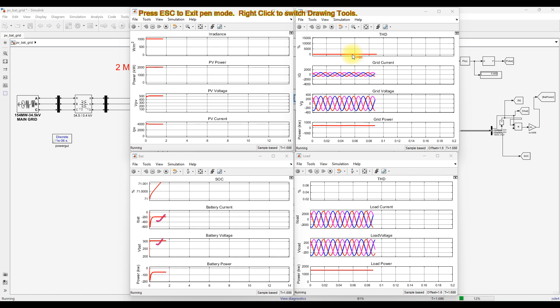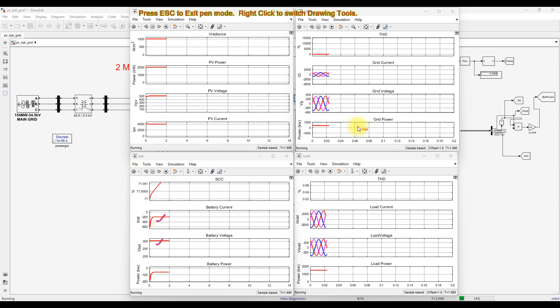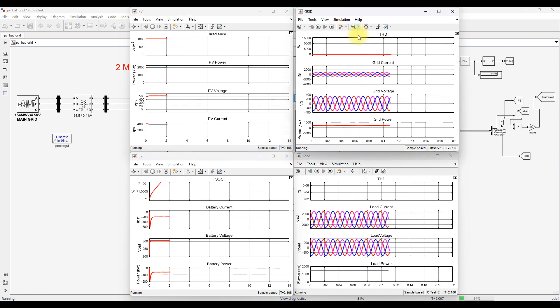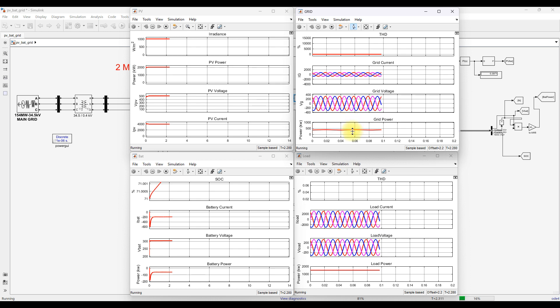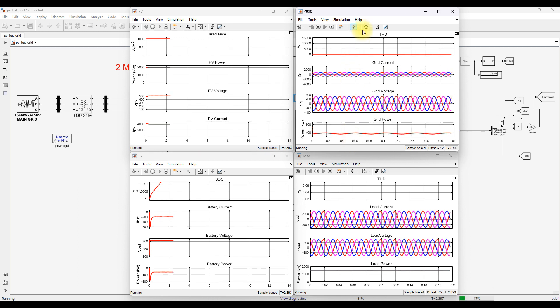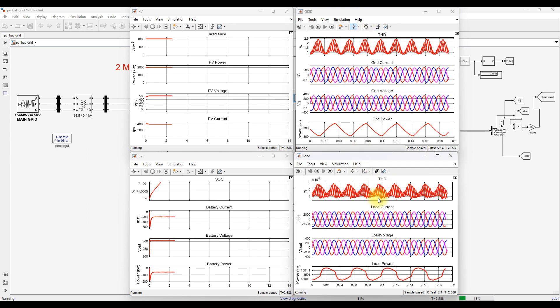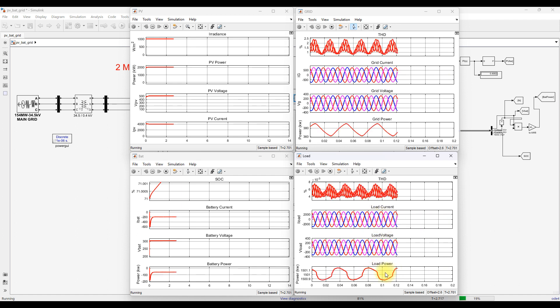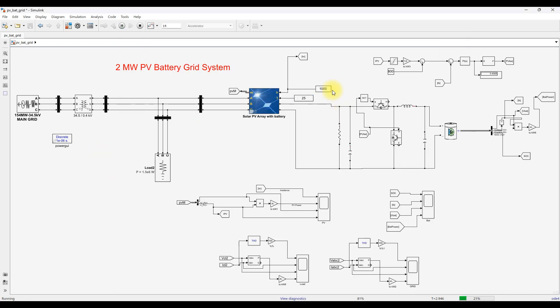Since the battery is charging, current and power are negative. The THD of the grid current is around zero, and the grid voltage waveform is sinusoidal. Grid power is around 400 kilowatts. Load THD and load current are shown, with load power around 1.5 megawatt.